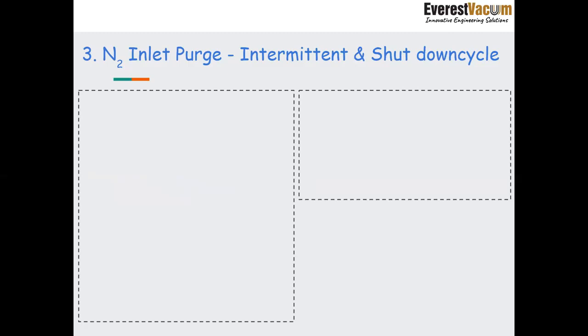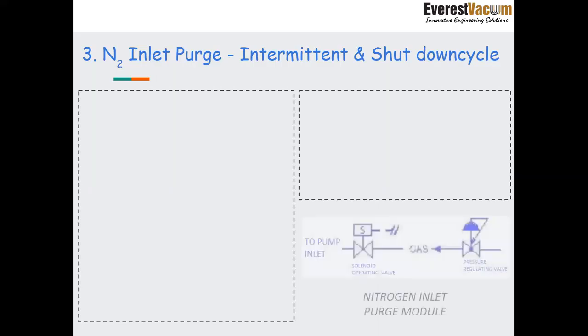Then another module is N2 inlet purge. There are two variants of it: intermittent and during the shutdown cycle. This is the basic nitrogen inlet purge module. There is a pressure regulating valve and a solenoid operating valve.